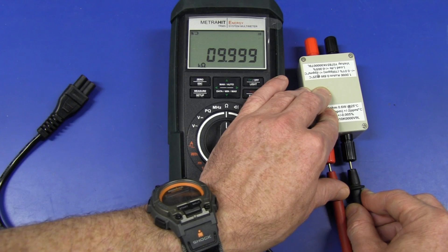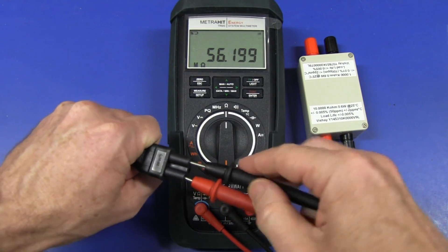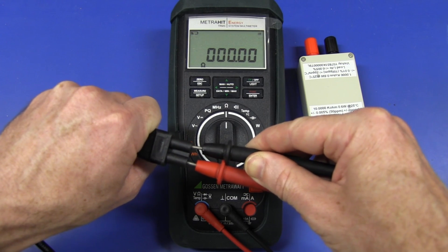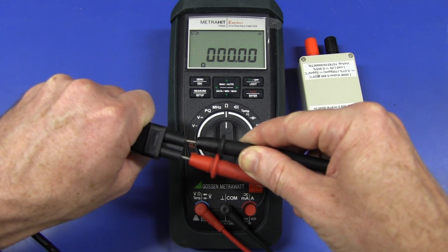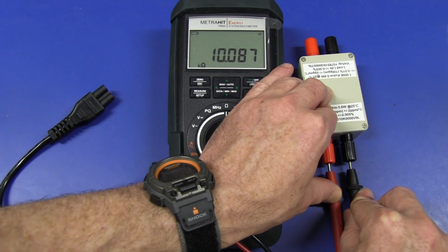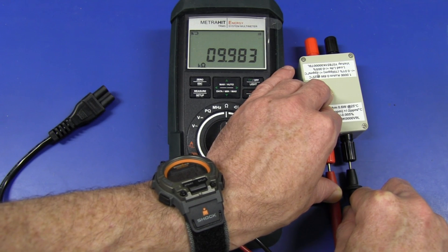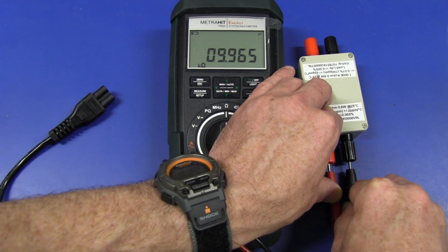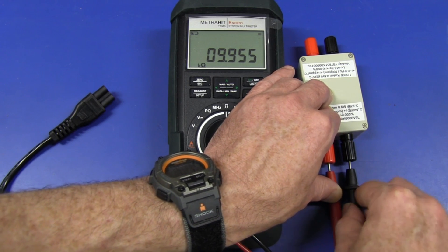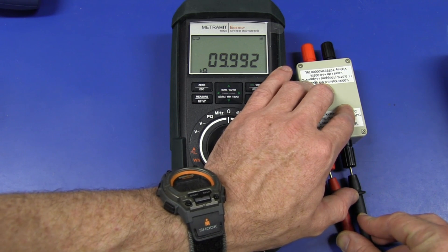And another Gossen Metrahit, but this time the Metrahit Energy meter. In we go. Let's see. This one just reads zero ohms, which is different to the Extra. So that's our 10 seconds up. That was fairly significant. But it recovers very quickly — it's gone on the negative side; it is playing around a bit. That's the first one that actually went negative. I'll have to see if that one comes good. And it slowly recovered, but this one actually took quite some time. So that's rather unusual.